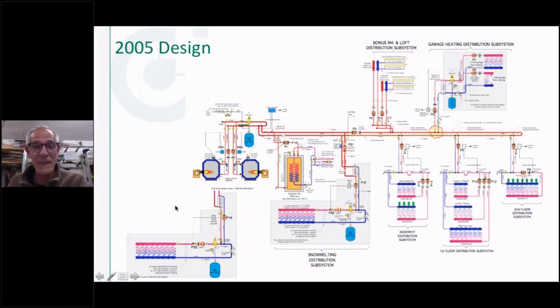So here's a drawing where we're going to clean up two things. Number one, we're going to change the pump so it's pumping away from the point of no pressure change, pumping into that flat plate heat exchanger, away from it. I don't know if the person that caught that on the last one is here, but thanks for pointing that out. And I'm going to show you an even better way of doing this, because this is obviously a pretty complex primary secondary, and this is a lot of work to put together with all these T's and calculating all this pipe size and the flow rate from the boilers and the distribution, your indirect. What if we could clean this whole drawing up and make it simpler for you for sizing this?